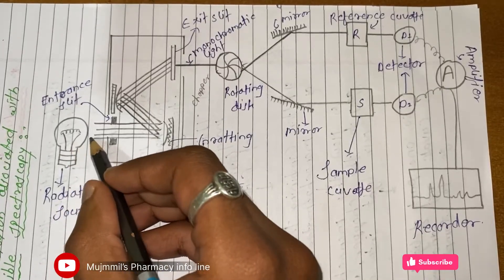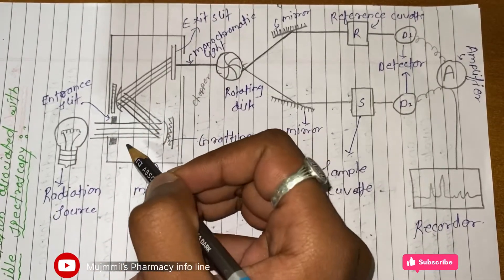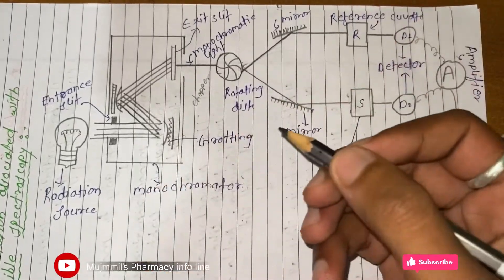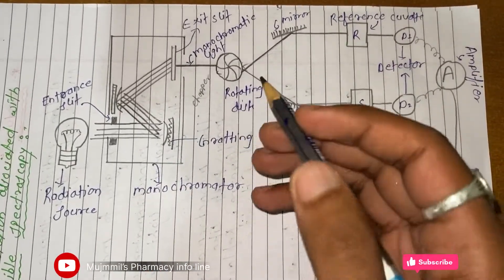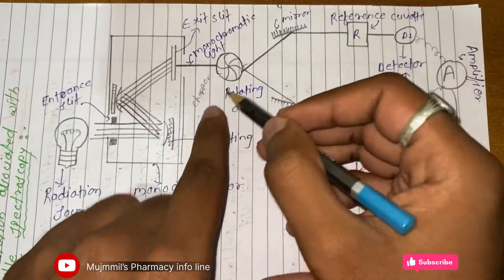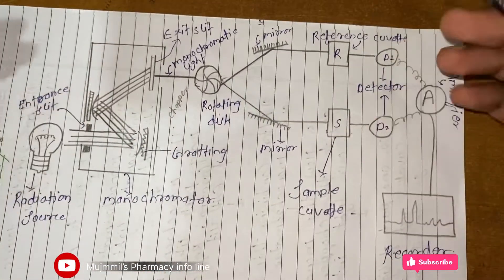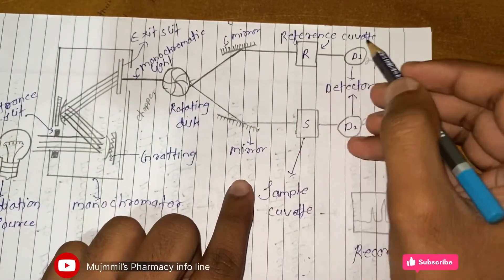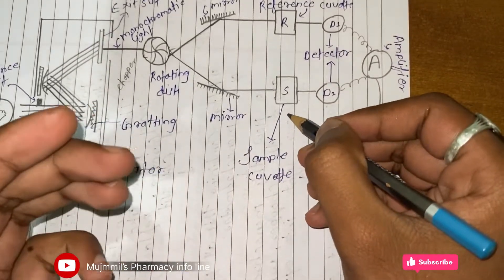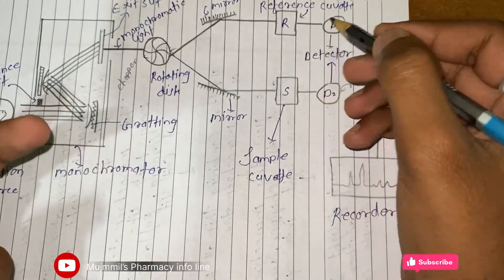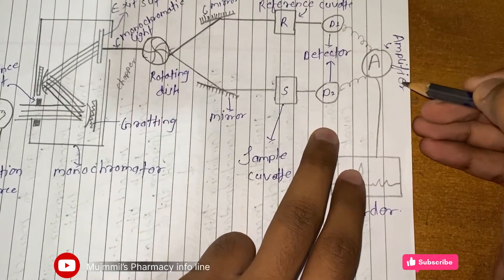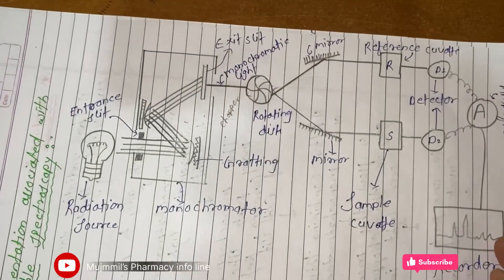The working: the radiation source emits polychromatic light, which must be converted into monochromatic light using the monochromator. The monochromatic light goes to the chopper, which divides it into two beams. Via mirrors, one beam goes to the reference cuvette and another to the sample cuvette containing the sample we are analyzing. The beams then go to the detectors, then to the amplifier, and finally the result is recorded.